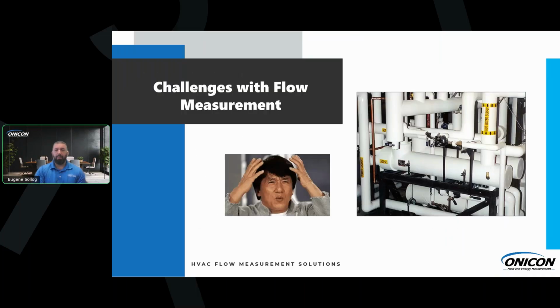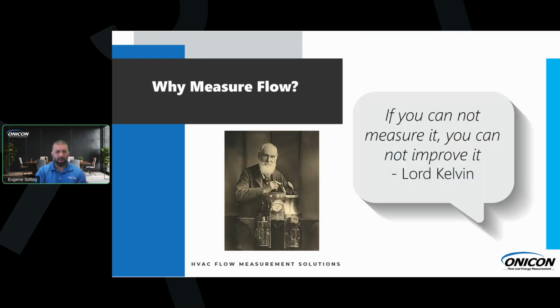So to jump into some of the challenges that we see with flow measurement. I know that sometimes you'll get into a mechanical space and you'll see something that looks like the picture on the right, and you don't know where to put the flow meter. The inline mag is by far the best choice of flow meter to put in something that looks like that, but it could still be very costly to put that in. So we're going to look at where our thinking is with these flow meters and other flow meters.